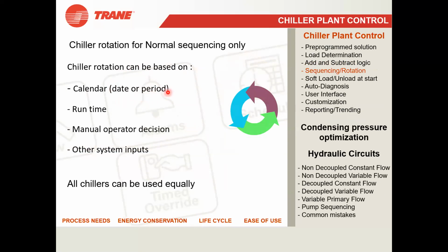We call it calendaring, and we can do this calendaring. From this period to this period, chiller 1 will be running. From this period to that period, chiller 2 will be running. That is called rotationing. Then runtime is a similar kind of thing: how much one chiller will be running. And then manual operator decision. Sometimes you do not want automatic mode, and you want to override it by manual operator decision, because you have an operator sitting there. Or if some problem has happened, you can overrule the automatic mode and run on manual operation.